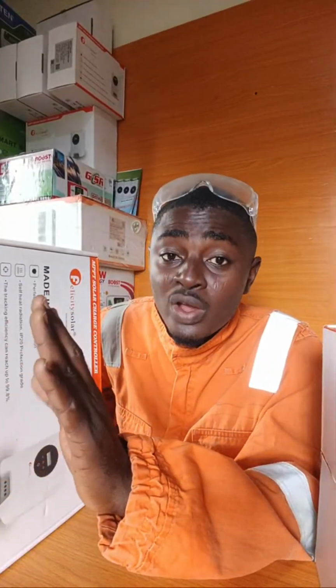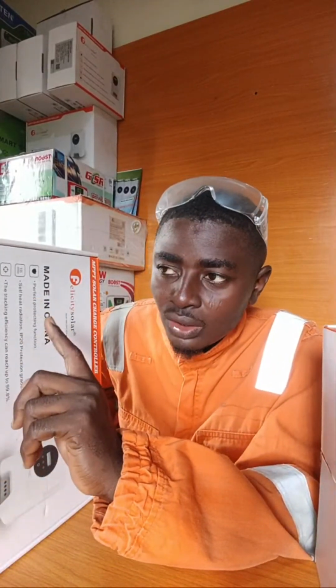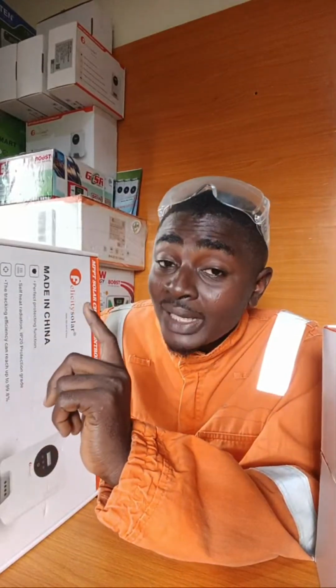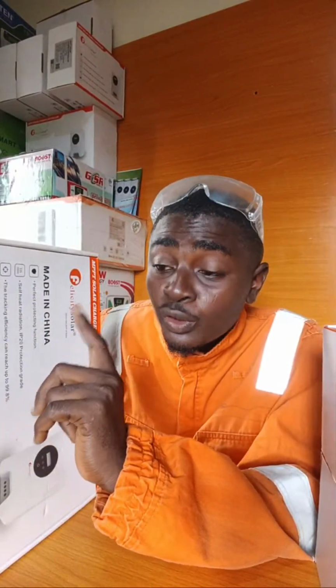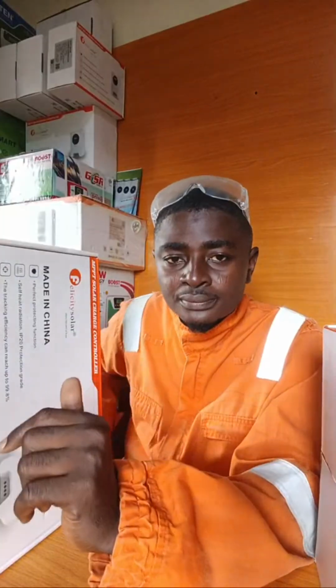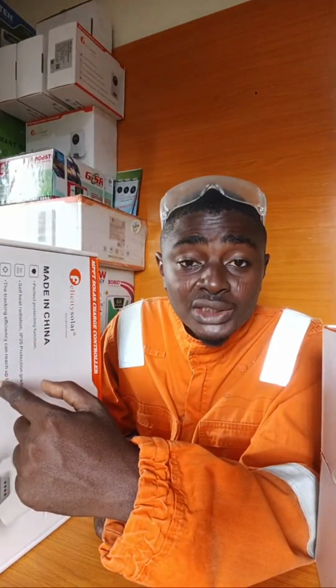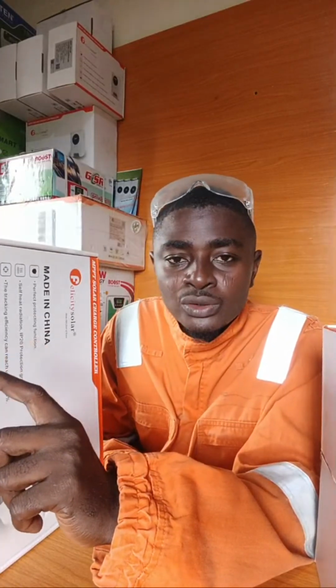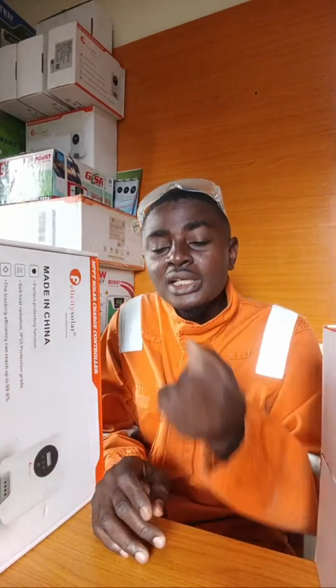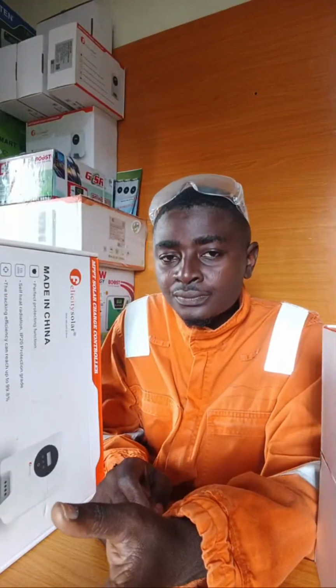You can stop it at 160, but they rate it at 170. Stop your VDC connection from the rooftop at 160. How do you get that? We have 12 of these panels connected to a 120 amps controller. The VDC of each solar panel is 40 VDC, and the VDC of this charge controller is 170 VDC. If we connect, we should not exceed 170. What's the perfect connection for this charge controller?